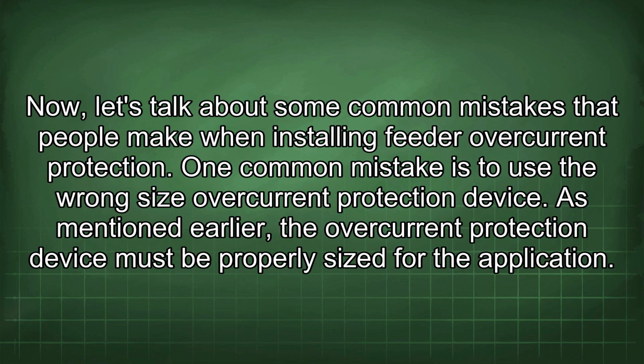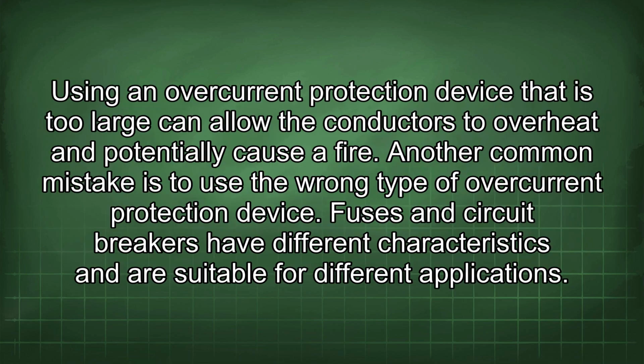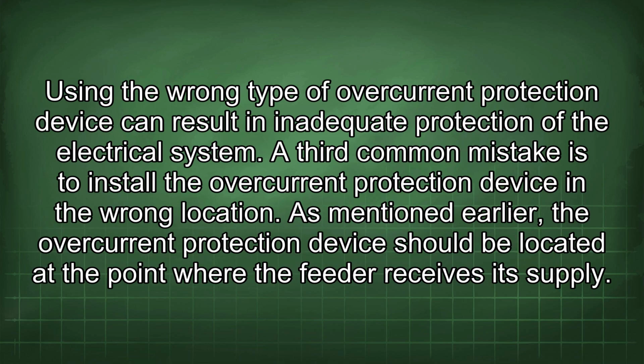One common mistake is to use the wrong size overcurrent protection device. As mentioned earlier, the overcurrent protection device must be properly sized for the application. Using an overcurrent protection device that is too large can allow the conductors to overheat and potentially cause a fire. Another common mistake is to use the wrong type of overcurrent protection device. Fuses and circuit breakers have different characteristics and are suitable for different applications. Using the wrong type of overcurrent protection device can result in inadequate protection of the electrical system.